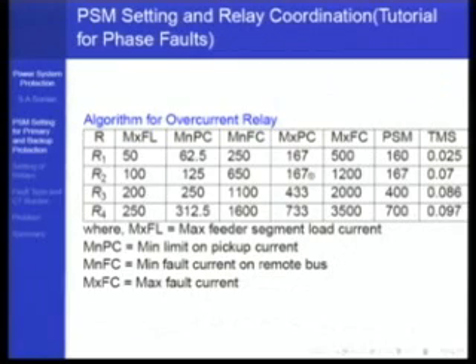Therefore the maximum pickup current is 250 times 2/3, which is 167 amperes only. So the maximum pickup is 167 and the minimum pickup is 125, and the pickup range has reduced a bit. Any number in that range can be chosen. To keep my life simple, I have tried to keep both these pickup values nearly close, so that I can play with TMS. So I choose 167.